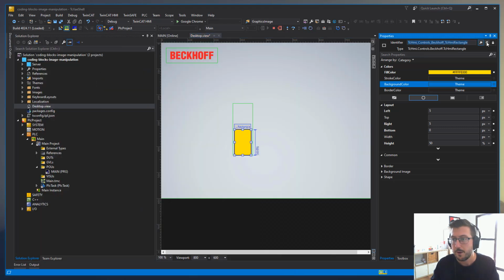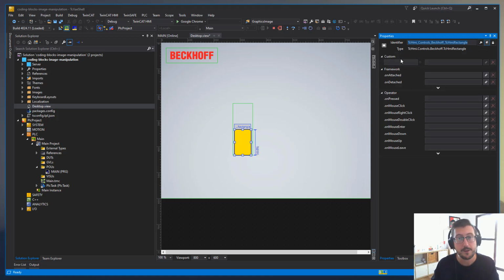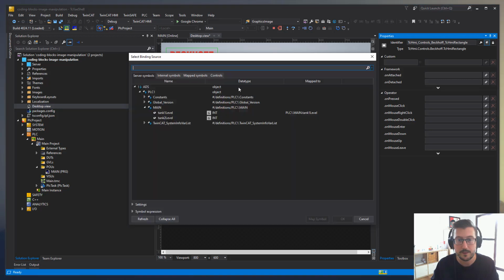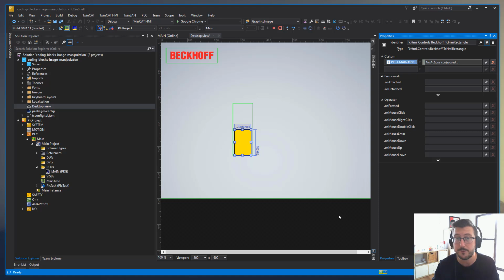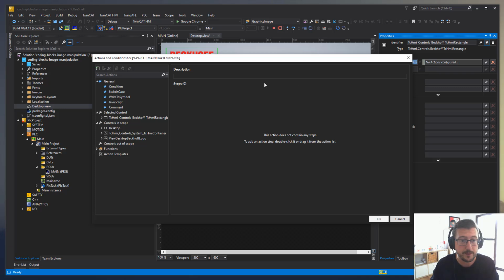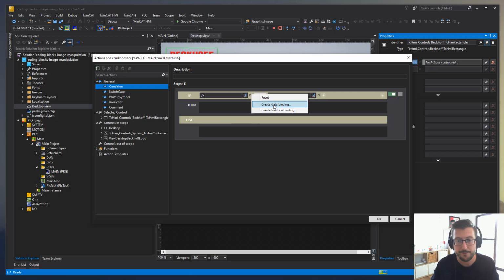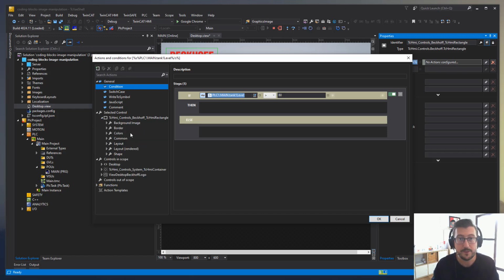Unpin that. I'm going to say that I want an event, and I'm going to have a custom event. And that custom event is going to be bound to tank level 1 changing. So it's only the fact that tank level 1 changed that makes this event fire. Inside the event, we're free to do whatever we like. So we could say things along the lines of, if tank level 1 is greater than 80, then what we can do is, one of the nice things of also doing it on the control itself is it prompts us to say, well, you are on this selected control.